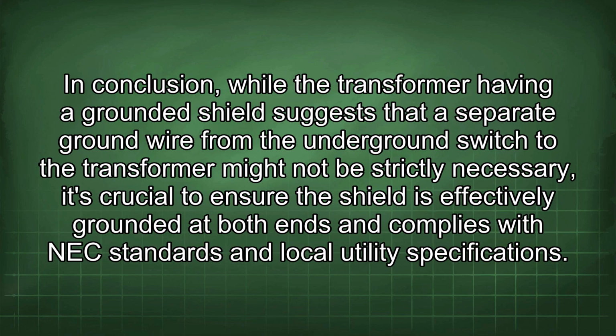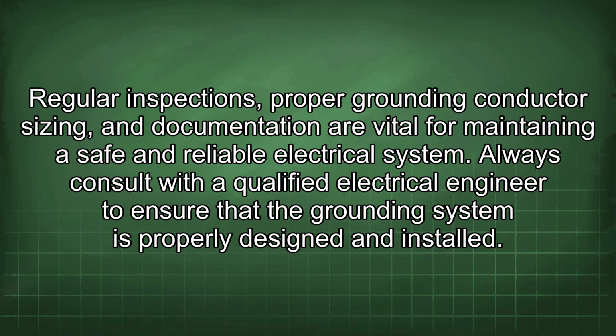In conclusion, while the transformer having a grounded shield suggests that a separate ground wire from the underground switch to the transformer might not be strictly necessary, it's crucial to ensure the shield is effectively grounded at both ends and complies with NEC standards and local utility specifications. Regular inspections, proper grounding conductor sizing, and documentation are vital for maintaining a safe and reliable electrical system. Always consult with a qualified electrical engineer to ensure that the grounding system is properly designed and installed.